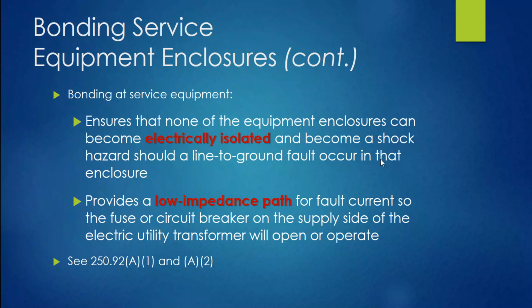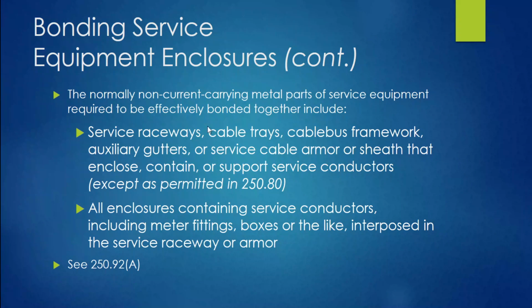Now, when you do that and you meet those requirements, it ensures that none of the electrical enclosures can become electrically isolated, an island to itself, which becomes a shock hazard when you come in contact with it. You could make the connection to where the intended path is back to the source. We don't want any metal to be isolated. We want it all bonded together. We want to give that fuse, if one is there, a fighting chance. This provides a low impedance path for fault current, so the fuse or circuit breaker on the supply side, the primary side of the electric utility, will open or operate. We hope that happens. Again, this is a regurgitation of what I just read for you out of the code. We're bonding all of these non-current-carrying metal parts together.